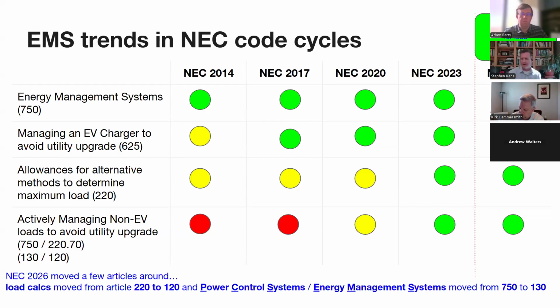Classically, power control systems before this code cycle were really about sources. For any solar and battery folks in attendance, we've used PCS to limit export in places where the grid is oversaturated with solar production—think Hawaii, parts of California, some other places. There are non-export rules from utility companies because grid operators can't handle too much solar, with the classic and infamous duck curve: overproduction of solar during the day and large loads coming on in the evening, creating an imbalance.